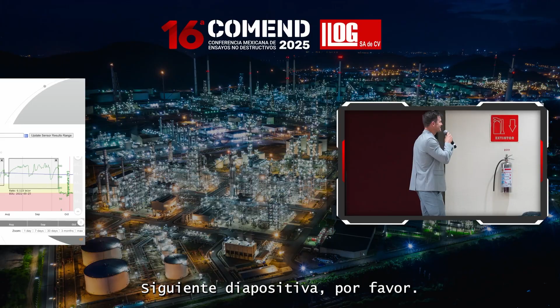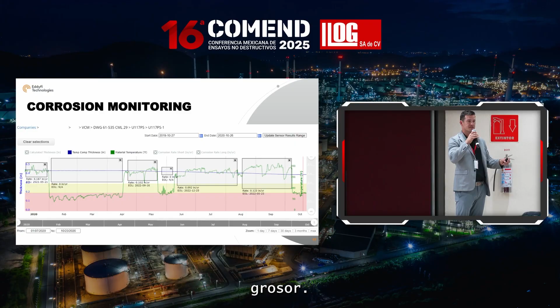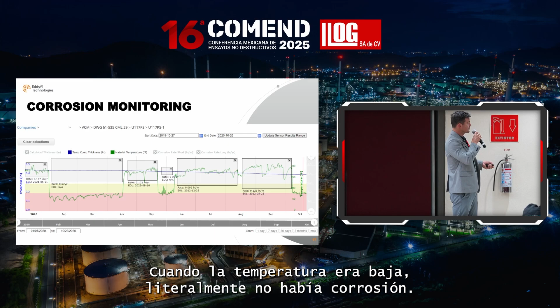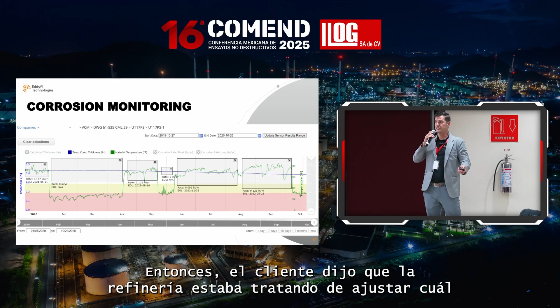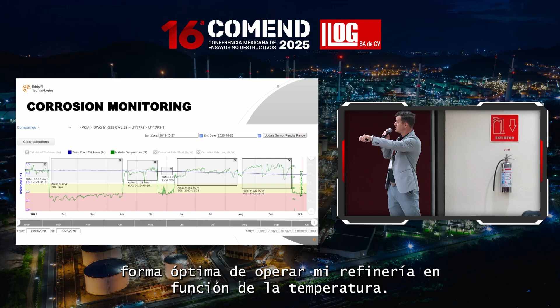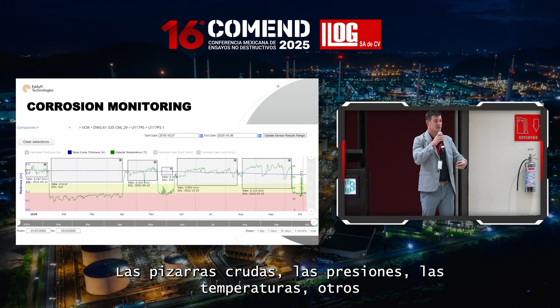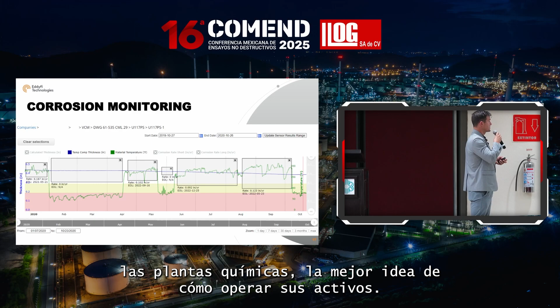Similar story here, except the other y-axis is temperature. These sensors take a skin temperature reading as well as a thickness reading, so you can start to correlate temperature versus corrosion rate. Over here, when the temperature was high, the corrosion rate was high; when the temperature was low, there was literally no corrosion. The refinery was trying to tweak the optimal way to run based on temperature, and you can see it adjusting. That's all coming just from the sensor. Crude slates, pressures, temperatures, and inhibitor dosing are other inputs stacked on top of this data to help give refineries or chemical plants the best idea how to run their assets.